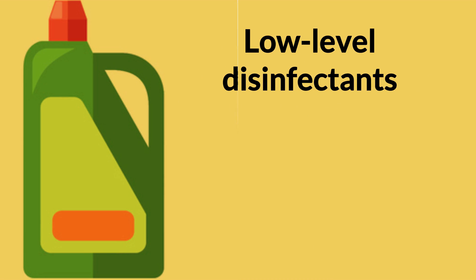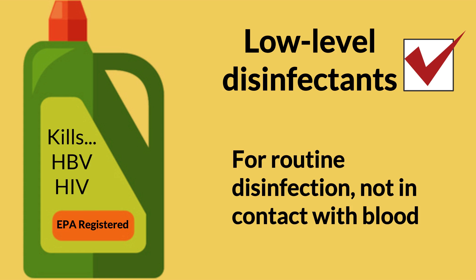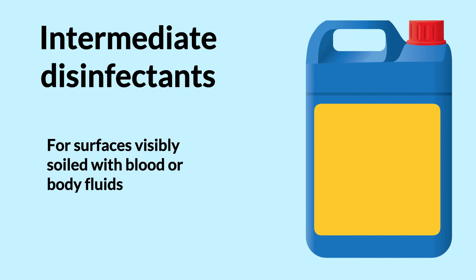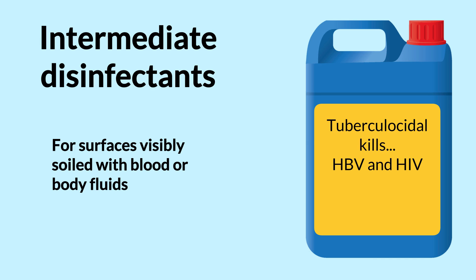When choosing disinfectants for dialysis facilities, low-level disinfectants such as any EPA-registered hospital disinfectant labeled as effective against hepatitis B virus and human immunodeficiency virus are fine to use for routine disinfection of surfaces that have not come in contact with blood. However, intermediate-level disinfectants must be available for disinfection of surfaces visibly soiled with blood or body fluids. Intermediate-level disinfectants will have a tuberculocidal, hepatitis B, and HIV label claim.